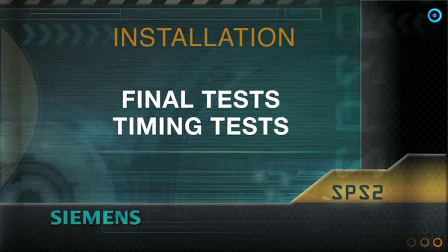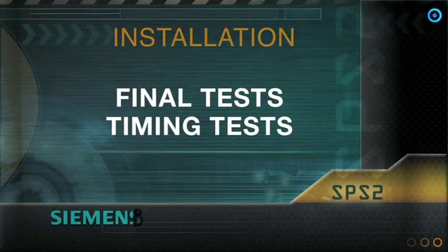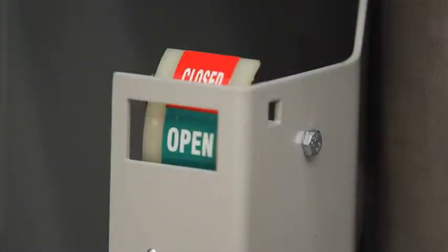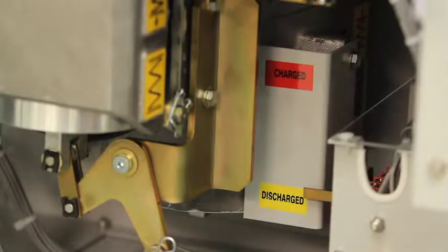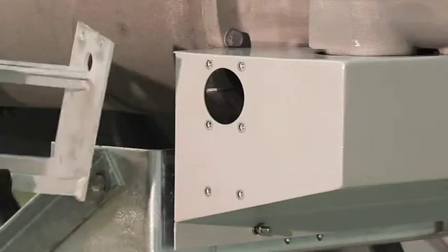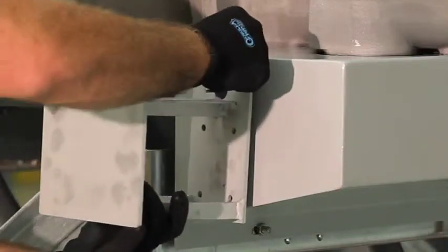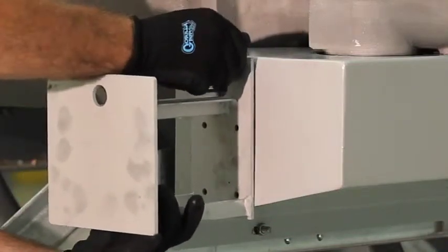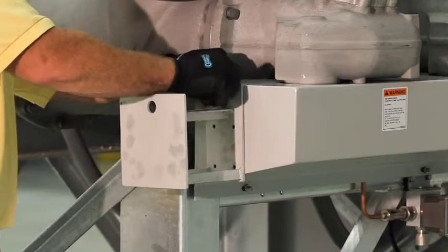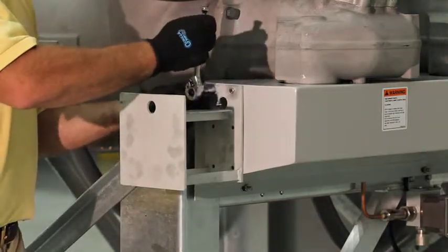Installation, final tests, timing tests. With the breaker open and the closing spring discharged, attach the travel transducer to the spring operator mechanism. A travel transducer may now be clamped into position with its rod attached to the pin on the linkage gear.